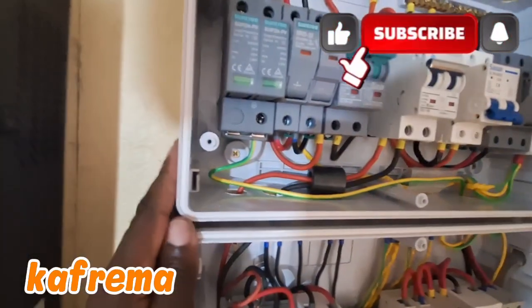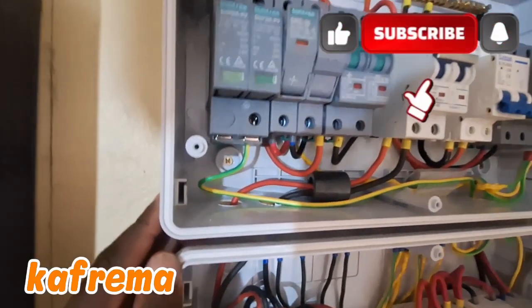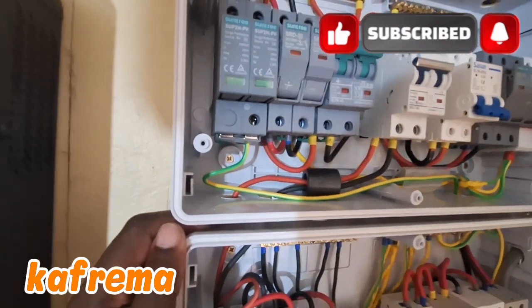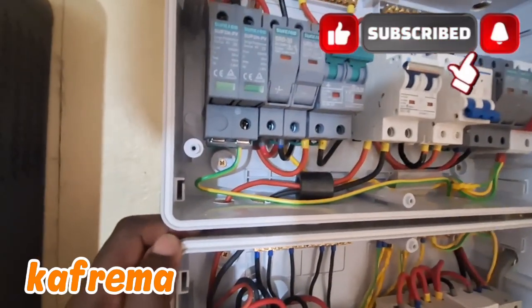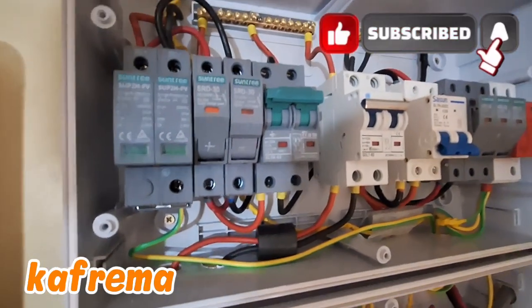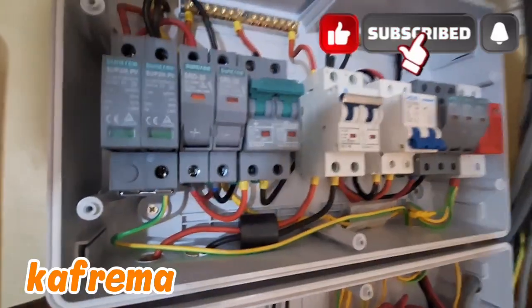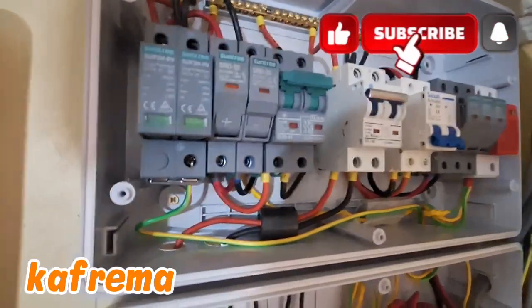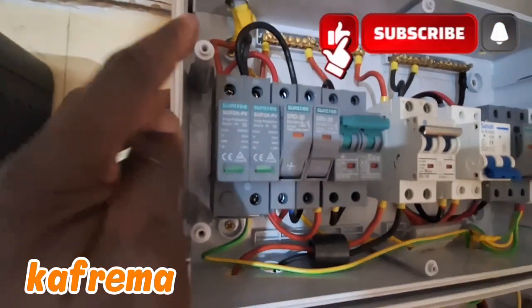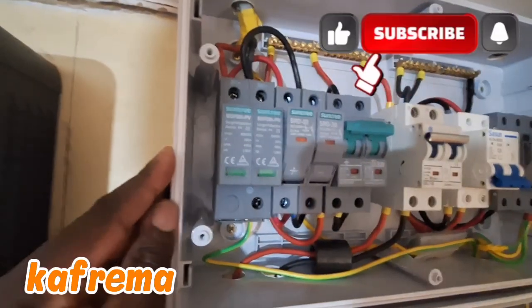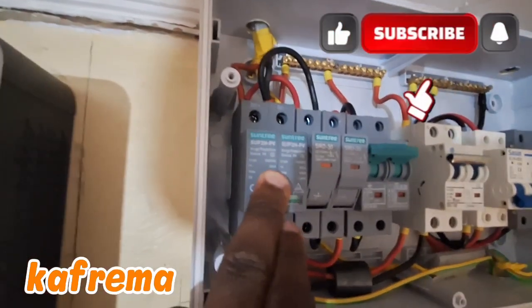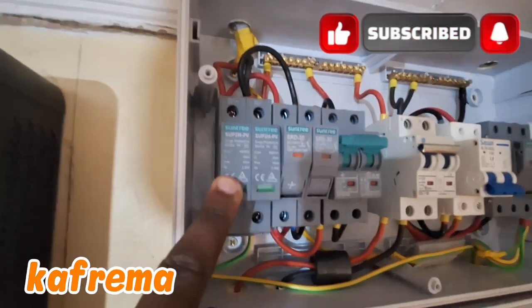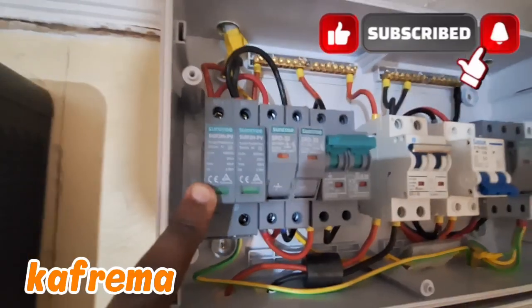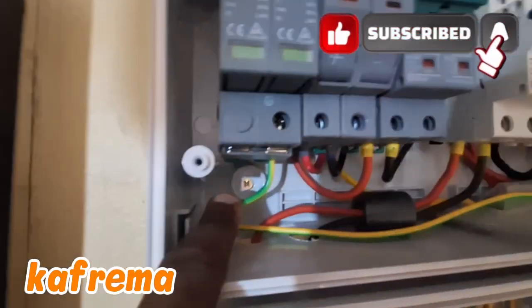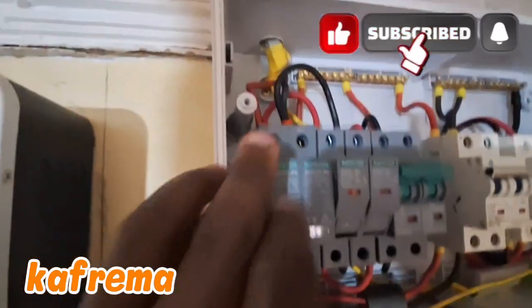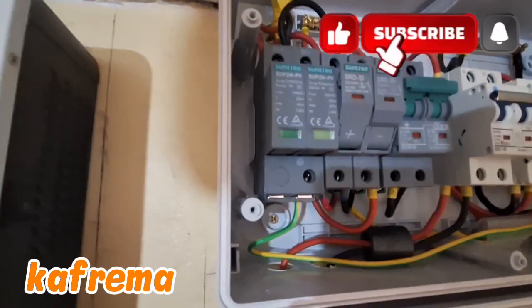DC has a very strong field around its cables. You understand? DC carrying conductors have a very strong magnetic, or electromagnetic, field around them. So we separate the two, AC and DC. In the DC box, this is where you receive the voltage from the solar panels. They come first to this, an SPD. That is a surge protection device. It protects if there is a lightning strike on the panels, on the solar array; it will be grounded. You see here below, it is connected to earth. Positive and negative here, then the other side is earth.